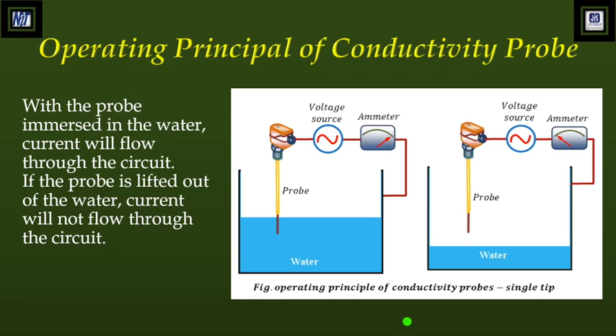The principle of conductivity is used to give a point measurement. When the water level touches the probe tip, it triggers an action through an associated controller. These actions may be to start or stop a pump, open or close a valve, sound an alarm, or open or close a relay. A single tip can only provide a single point action.